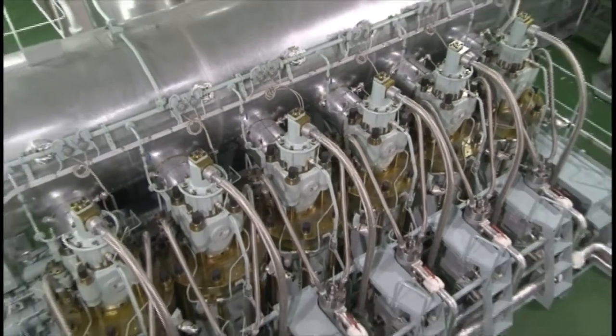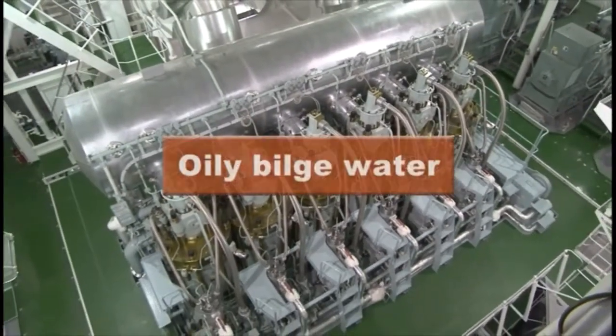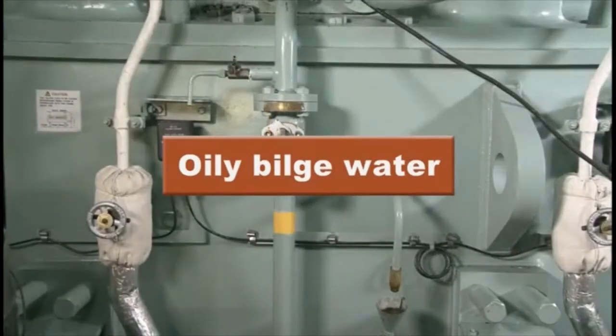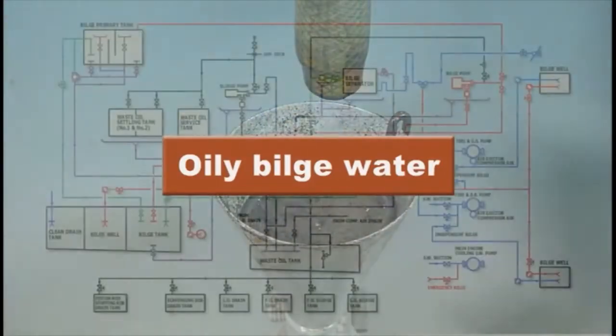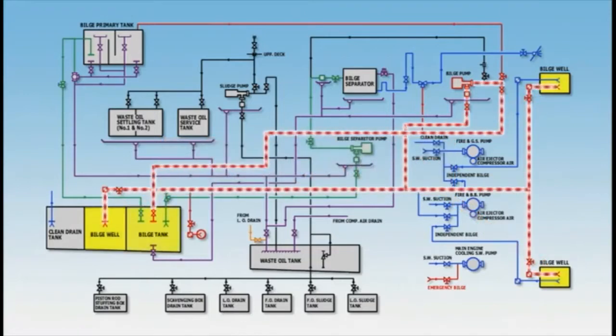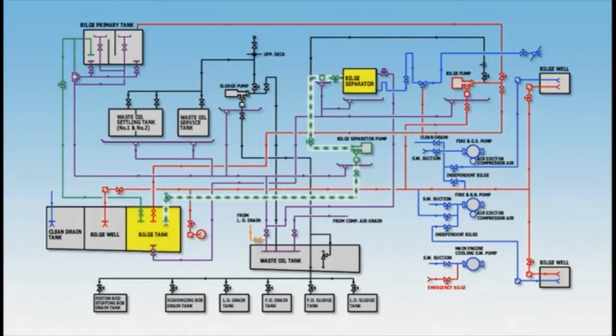Ship's bilge is roughly divided into two types according to their source. One is oily bilge water, composed of water and oil that leaks from engine room pipes during daily operation of machinery and during maintenance work. Oil and water leak out and mix together to create oily bilge water, also known as drainage bilge. This fluid is collected in a bilge well or in the upper section of a bilge tank. Oily bilge water is collected in the bilge tank, then transferred to the bilge separator where oil content is removed, and the water is discharged overboard.